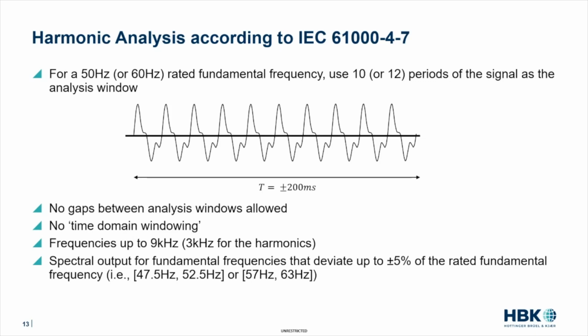But what the standard prescribes is that the measurement equipment or the device that you are measuring with should be able to handle at least plus or minus 5% of the nominal frequency. So in practice, that means that when you're measuring nominal 50 hertz systems, you should be able to handle frequencies from 47.5 to 52.5 hertz, and for 60 hertz systems from 57 hertz to 63 hertz. So those are, let's say, important things that the standard prescribes on how you should measure harmonics. There are more details, but I'm not going into that because they're not so relevant.